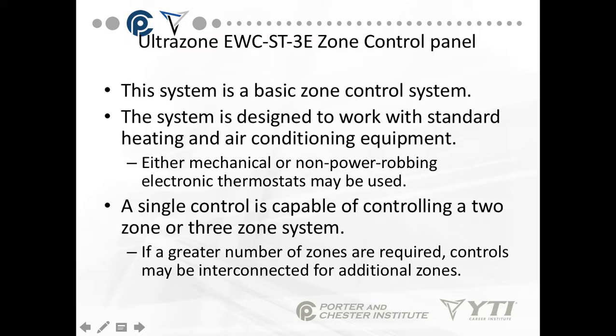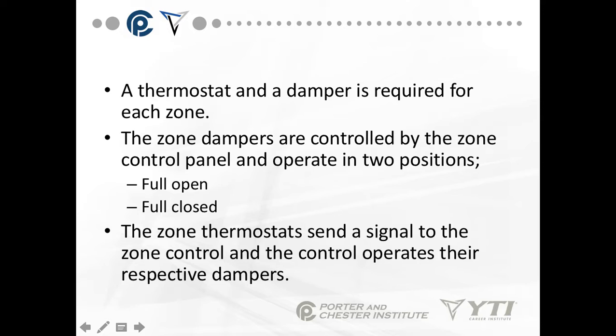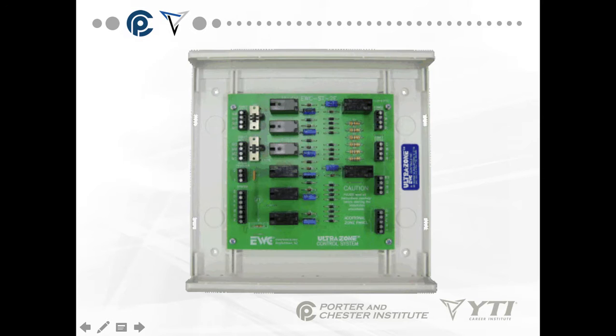If a greater number of zones are required, the controls can be interconnected for additional controls. A thermostat and a damper are required for each zone. The zone dampers are controlled by the zone control panels and operate in two positions — full open or full closed. There's no midway on these.